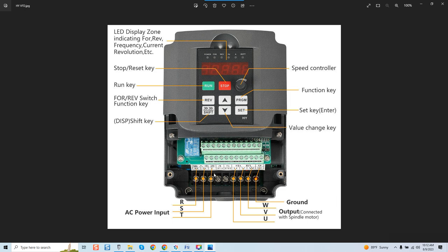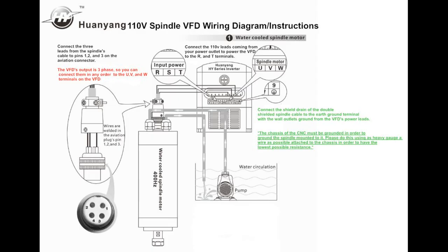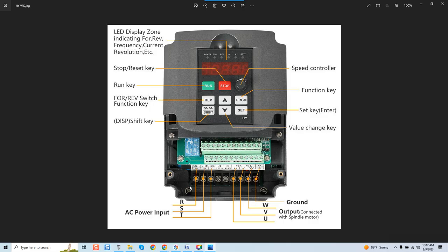You have your RST here and that's going to be for your live leads going in. Now if it's 220 you're naturally going to have two power leads coming in and then your ground lead over here. Now if you don't have 220, if you have 110 volt you'll have a live and a neutral and that would be coming on this side and the instructions with the VFD will explain to you how to connect that.